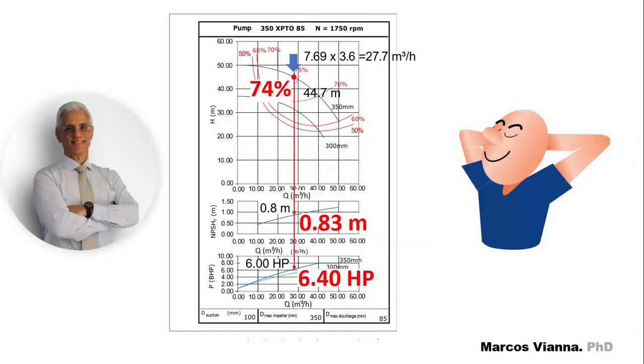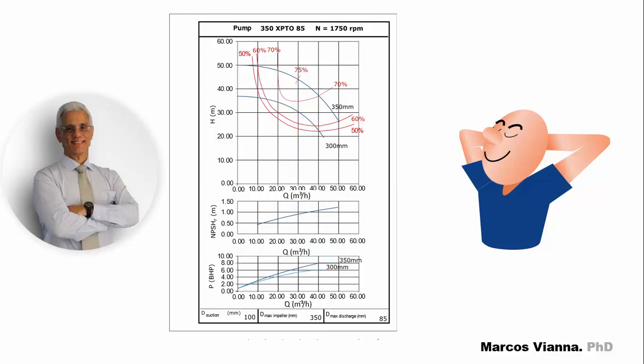Here are the values that we find by referring to the pump chart and the values that we found with our functions. Not bad, what do you think? Now we're able to solve problems in which we'll associate pumps, systems, modify the speed of the pumps, and the diameters of their impellers. As you can see, there's a lot of new videos coming on.